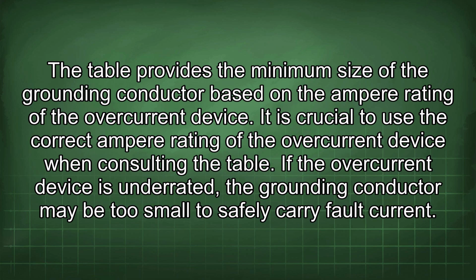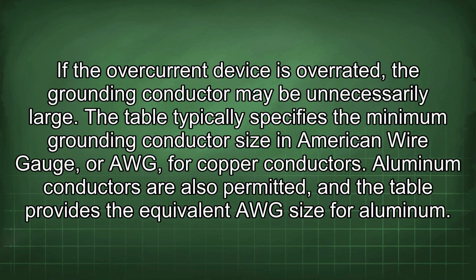If the overcurrent device is underrated, the grounding conductor may be too small to safely carry fault current. If the overcurrent device is overrated, the grounding conductor may be unnecessarily large. The table typically specifies the minimum grounding conductor size in American wire gauge, or AWG, for copper conductors. Aluminum conductors are also permitted, and the table provides the equivalent AWG size for aluminum.